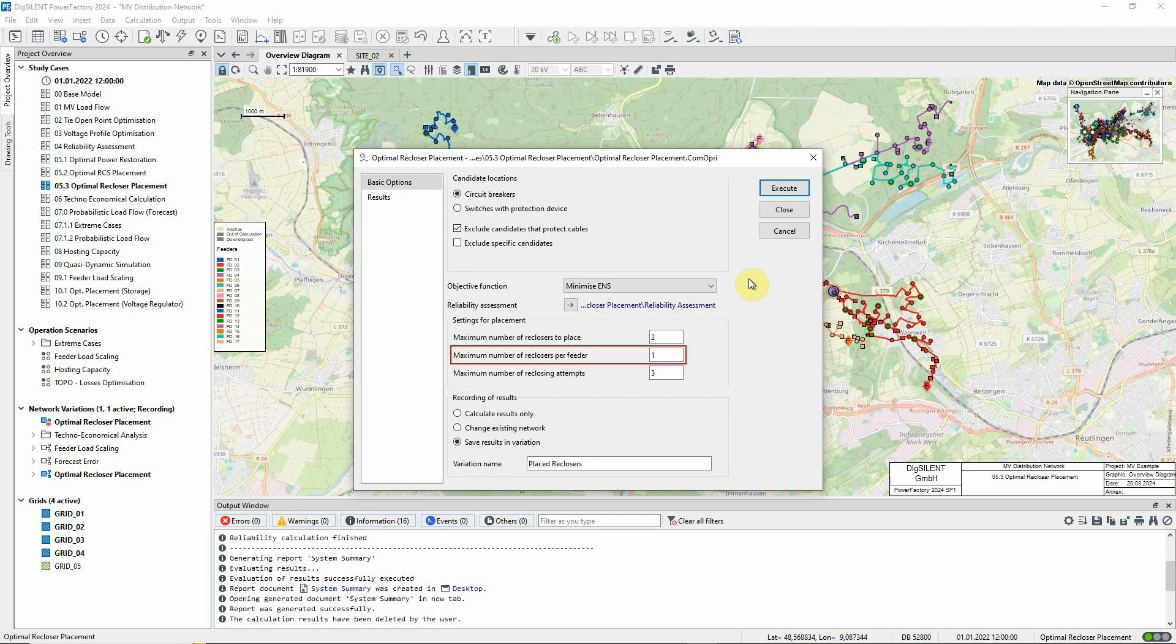This setting means that no more than one recloser will be placed in any one feeder. And this number is used when assessing MAIFI, the Momentary Average Interruption Frequency Index. It will also be used as the setting in any switch that is identified as a new recloser.